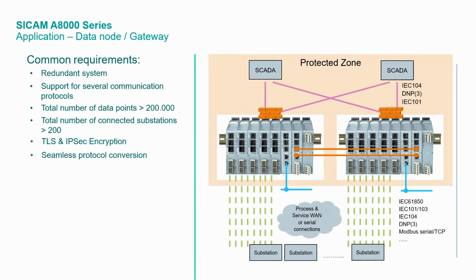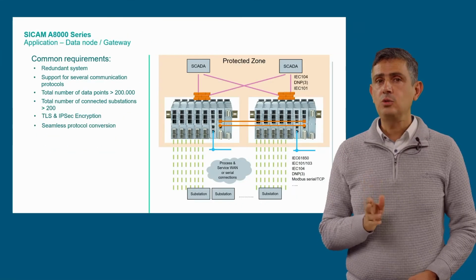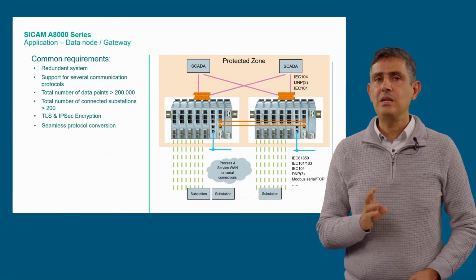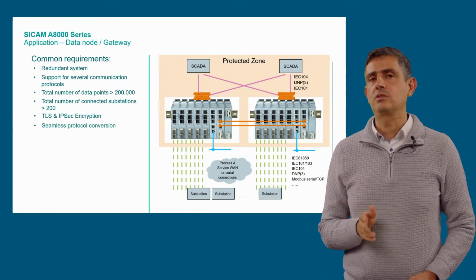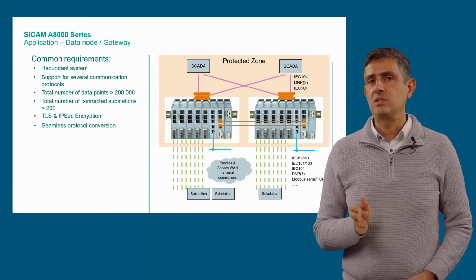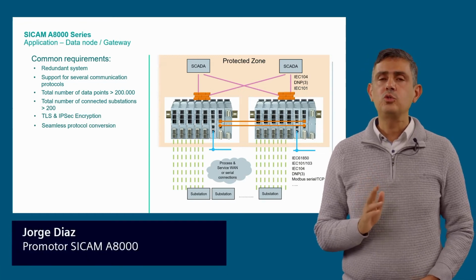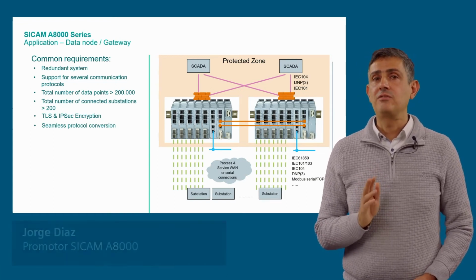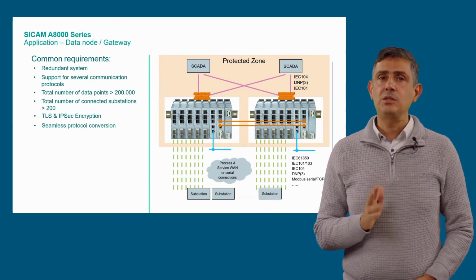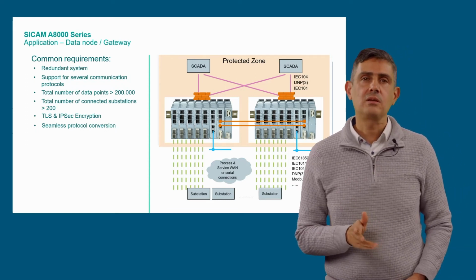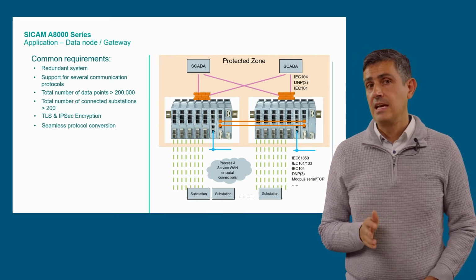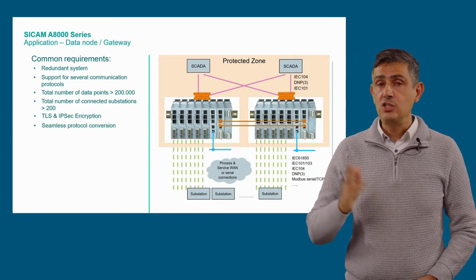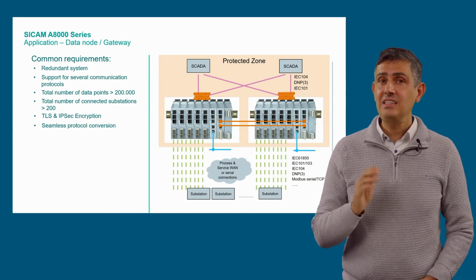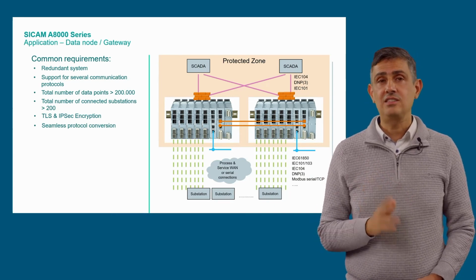This application normally requires a redundant system, since the communication between the upper and lower system is always critical. The data node must support several communication protocols and must be able to transfer a large amount of data points. The amount of subsystems or substations that must be connected to the data node could be quite large. To prevent man-in-the-middle attacks, TLS encryption is also a normal cybersecurity requirement for the provided communication. Since the amount of data to be converted is huge, it must be done seamlessly by the data node to prevent communication jamming in the system.